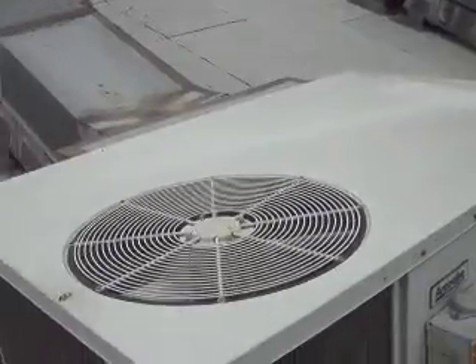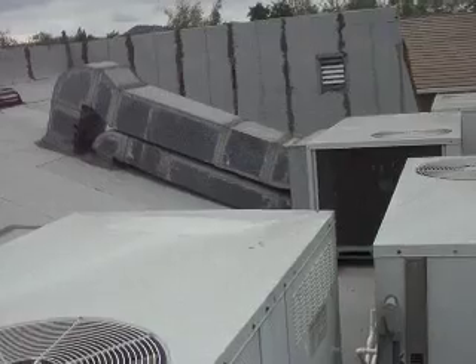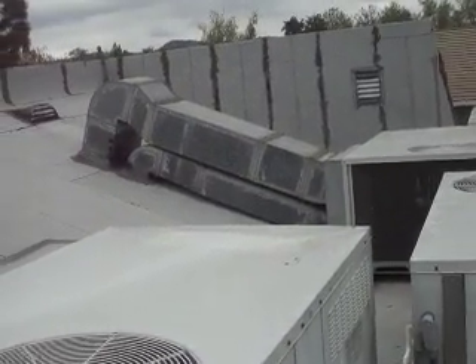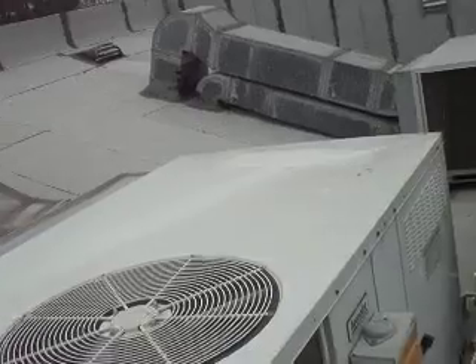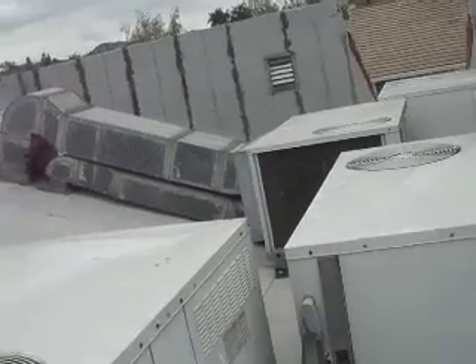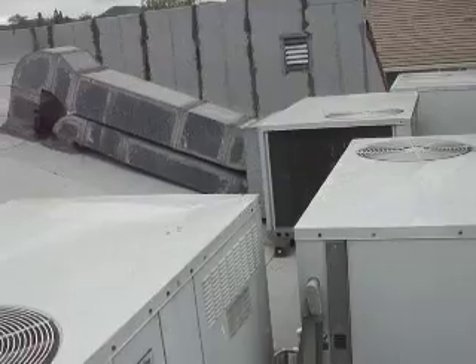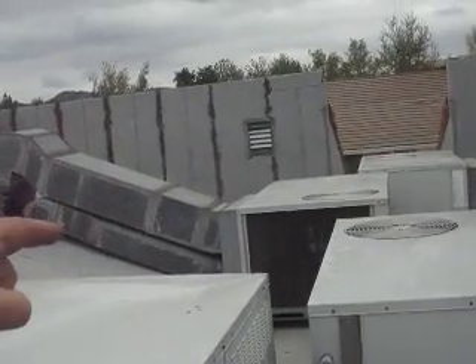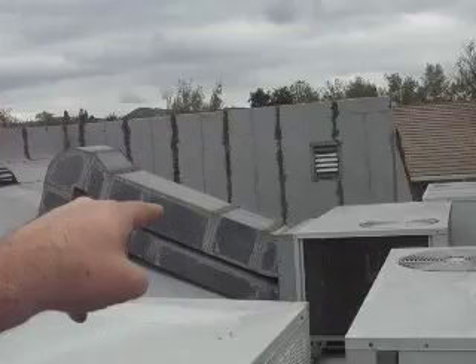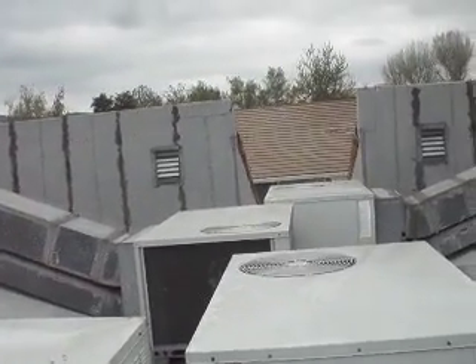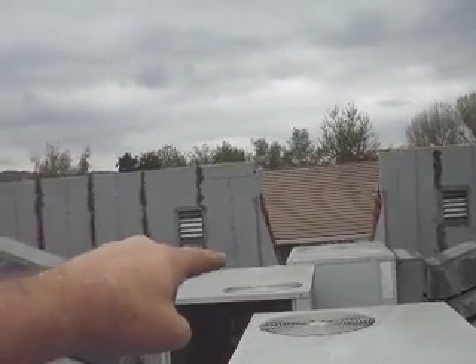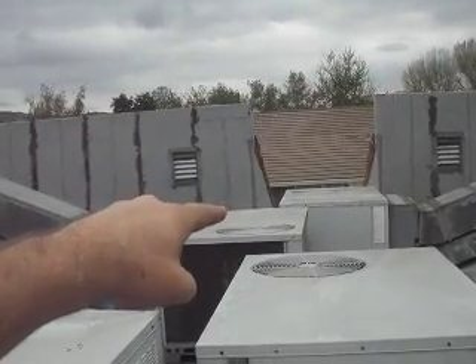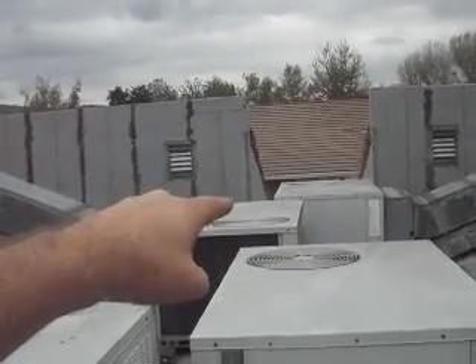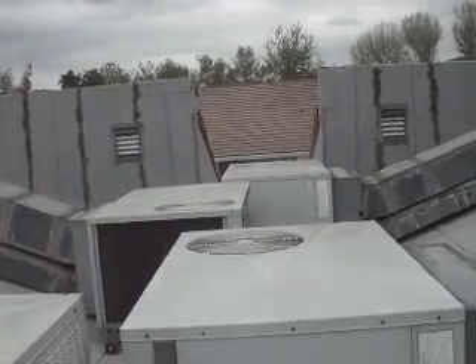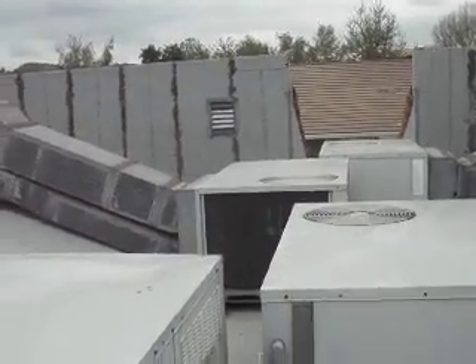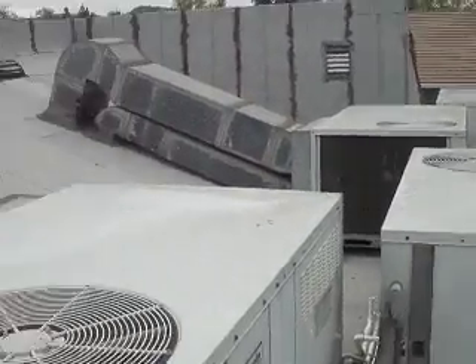But I've got three that are problematic with the coils and refrigerant leaks, and I've run sealant. I braze up whatever leaks I can access and find, but most of them are occurring within the coils. I replaced one coil for Theater 2 in this middle unit. The one in the back has been leaking. It hasn't been so bad, but it does leak, and it's a little bit low right now. I've got to recharge that and run some more sealant through there. Sometimes it works, sometimes it doesn't.